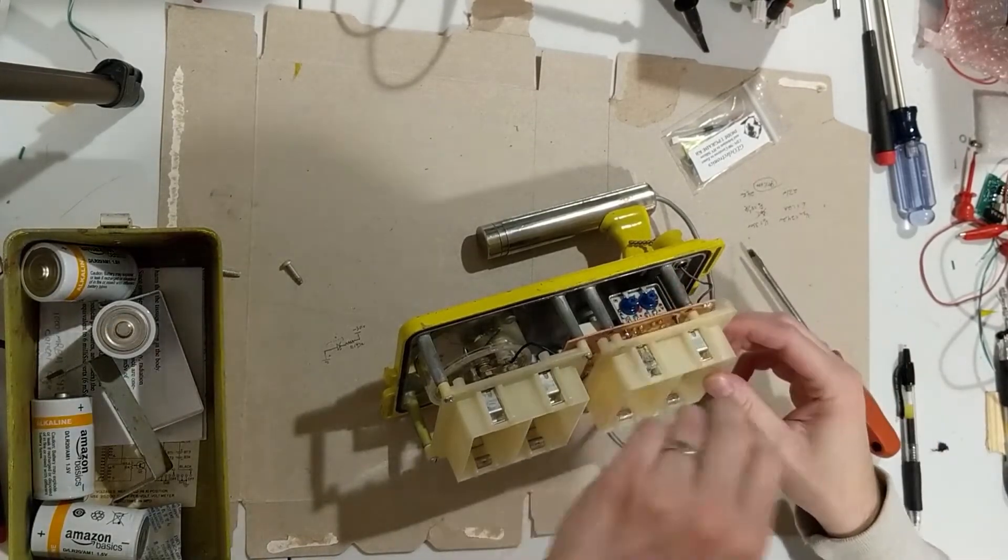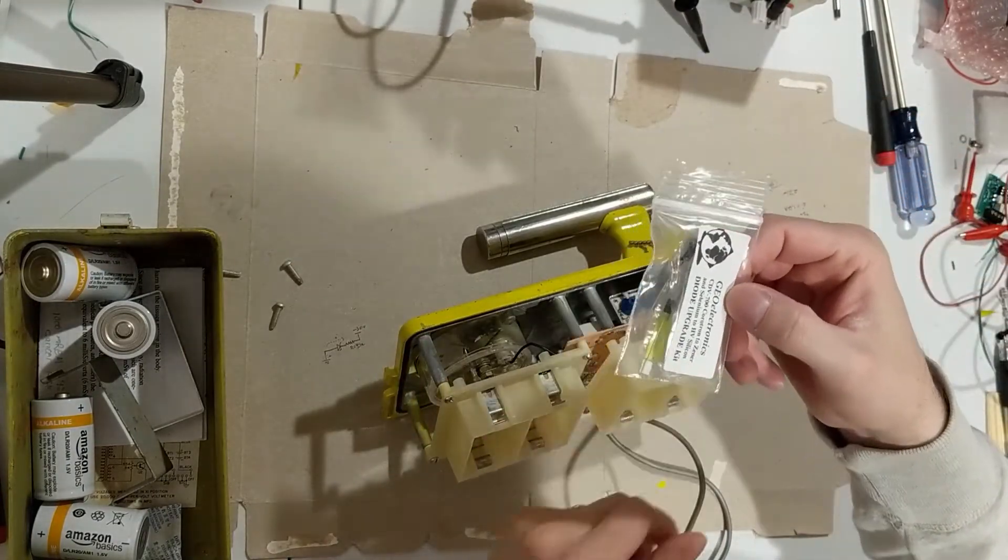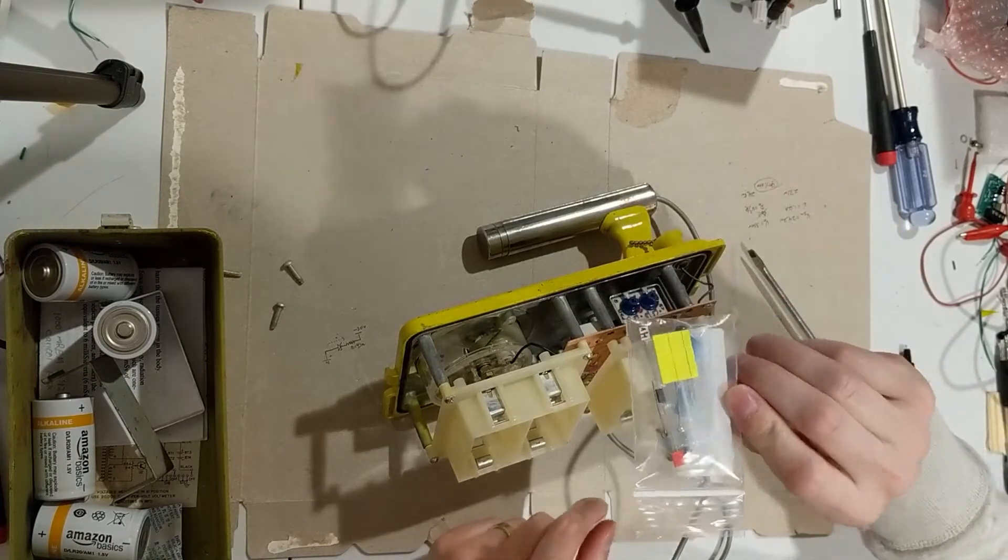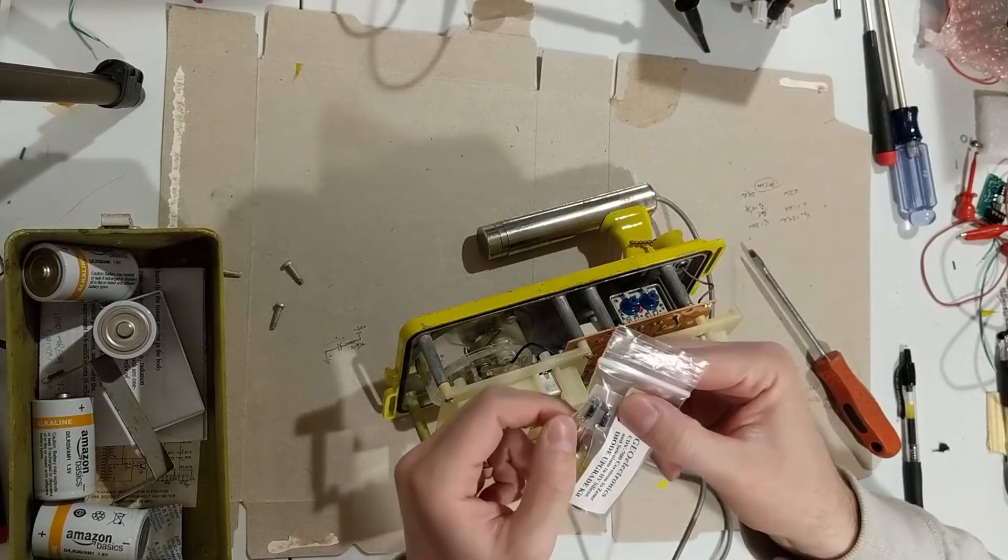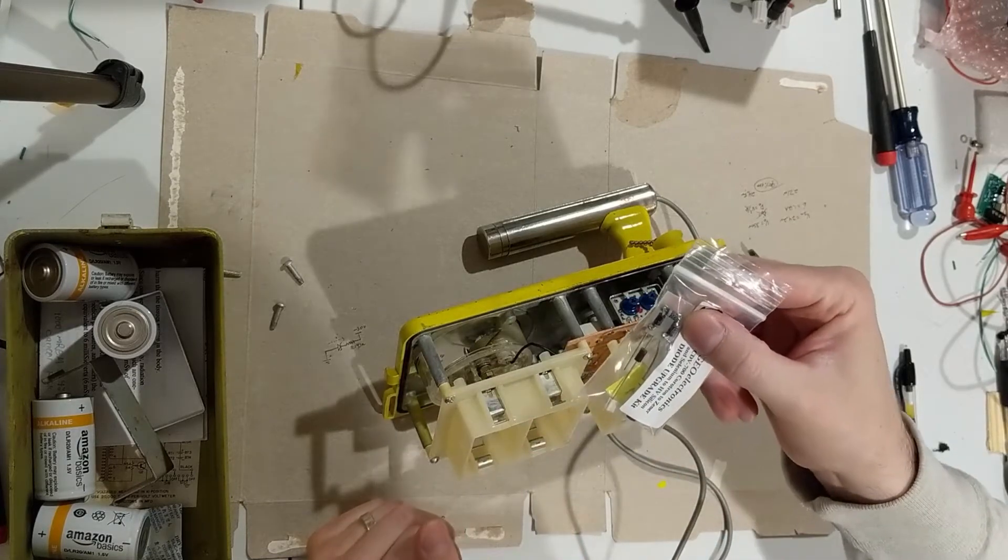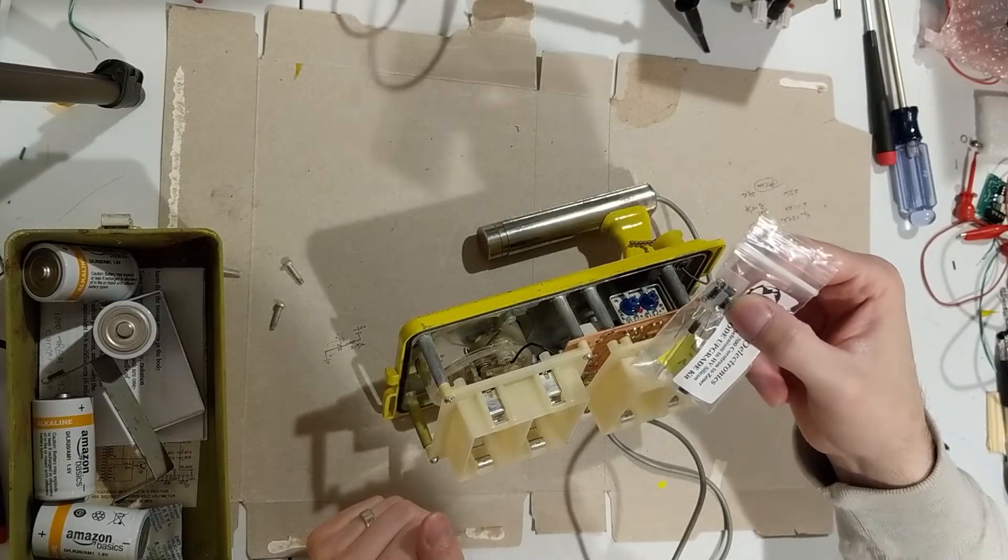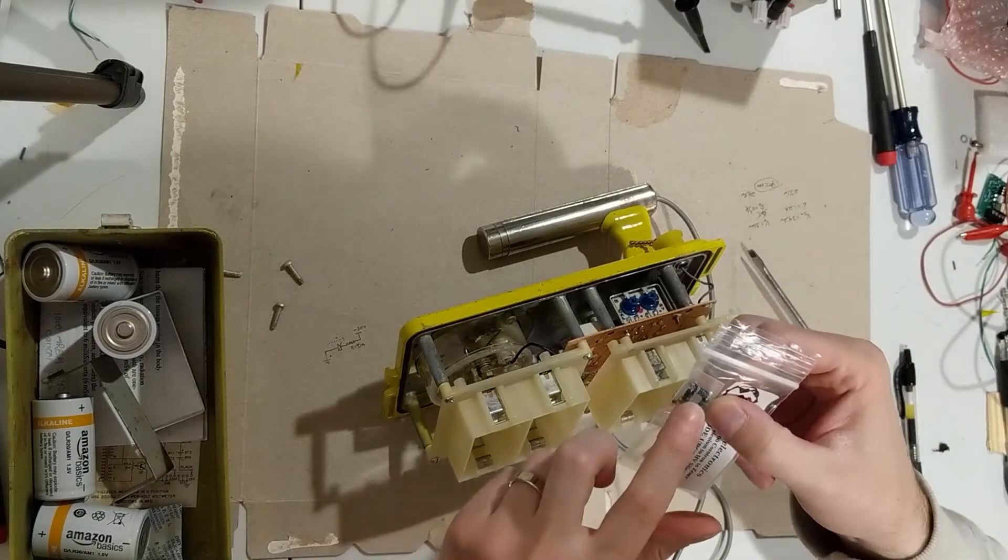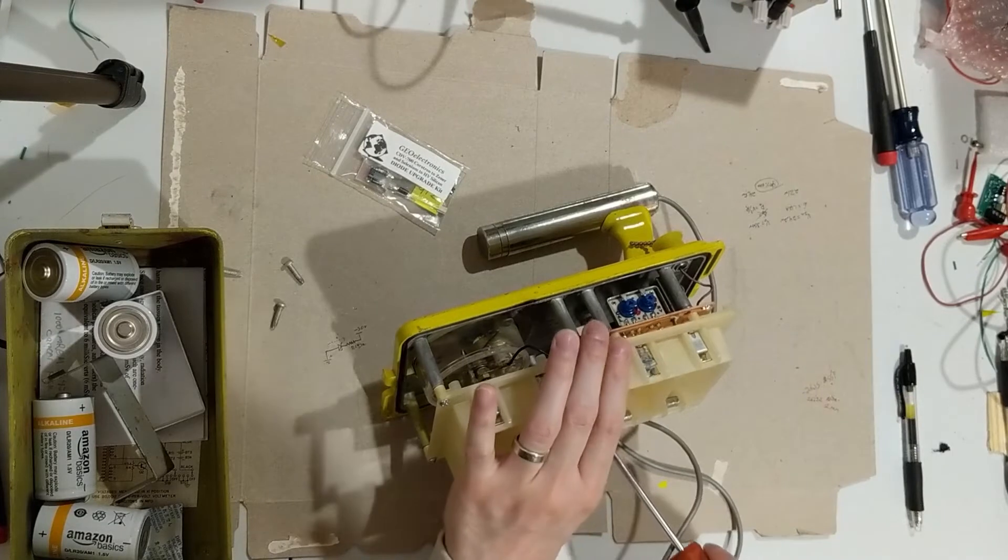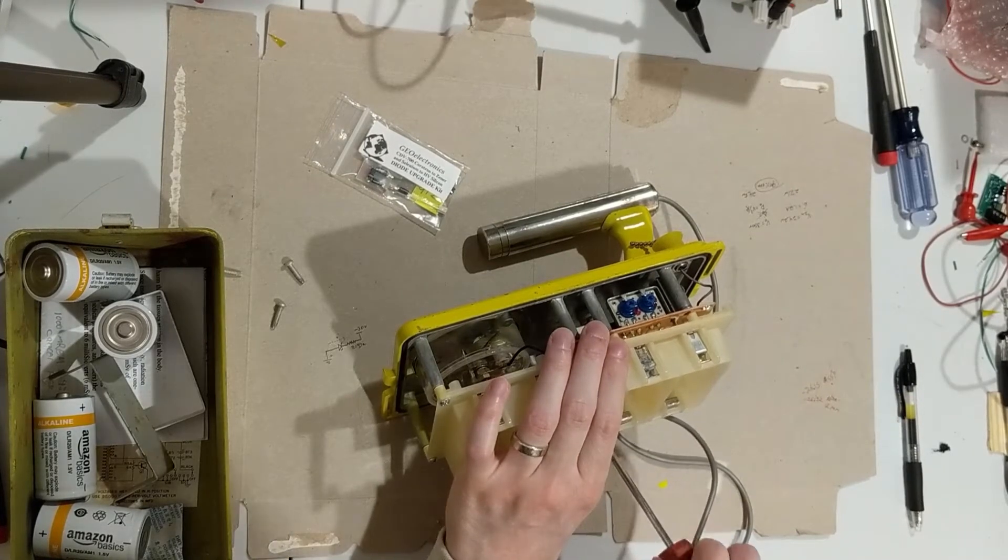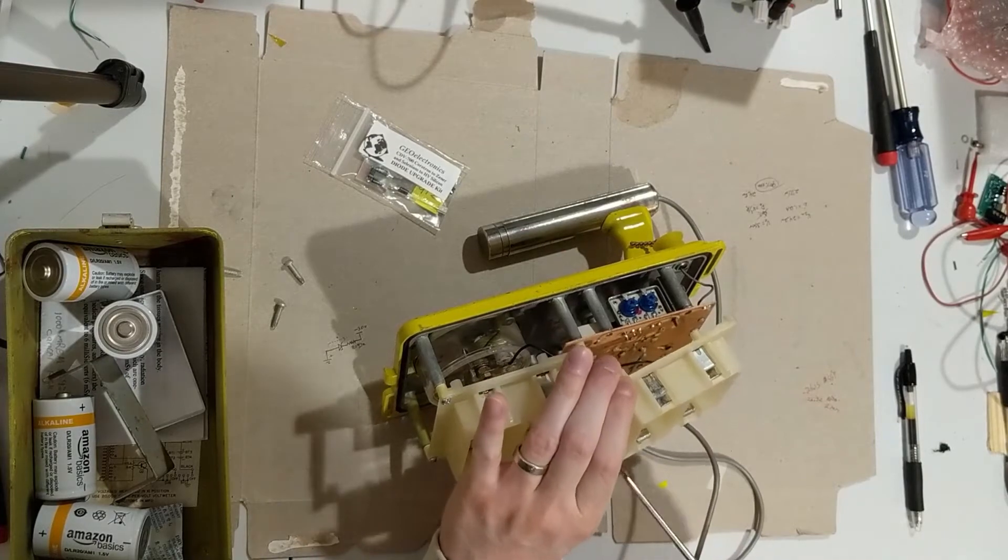There's a lot of other common things if you read on the internet, bad solder joints, et cetera. I'm hoping I don't have to get that far into it. I found on eBay a company, Geo Electronics, that sells small upgrade kits. Essentially it has a modern diode and what I'm hoping to be an acceptable replacement for the Corotron. Typically you end up stacking zener diodes together to get about 920 volts. This one looks like it might be a little below that, but we'll see how it works out. Worst comes to worst, I have to add one more zener diode to that stack.